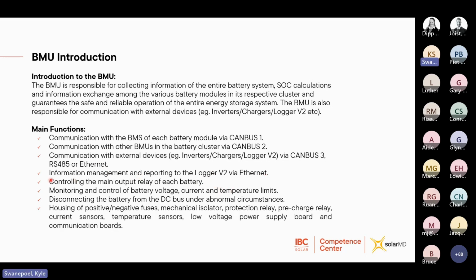And each BMU is responsible for controlling the main output relay of each battery. So if the battery is in safe operating conditions, the relay will be closed, which means that you can charge and discharge the battery. If not, the relay will open and wait for the conditions to be met again before closing the relay. And then the BMU monitors each of those battery modules. So the battery's voltage, the current, as well as the temperature limits are taken into account. And it will disconnect the battery from the DC bus under abnormal circumstances.